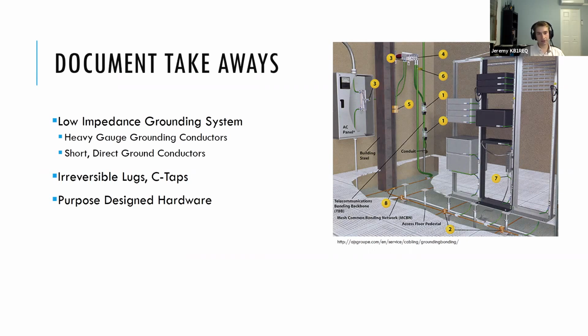And so how do you get that? You get that by grounding with heavy gauge conductors. The smallest gauge wire that's mentioned in relation to grounding in R56 is number 6. That's the minimum that you can use and be compliant with that standard. And then as you get longer runs of ground cable, NEC 250 dictates that you've got to get coarser and coarser, larger and larger with that cable. So when we're talking about grounding, we're talking about heavy conductors.